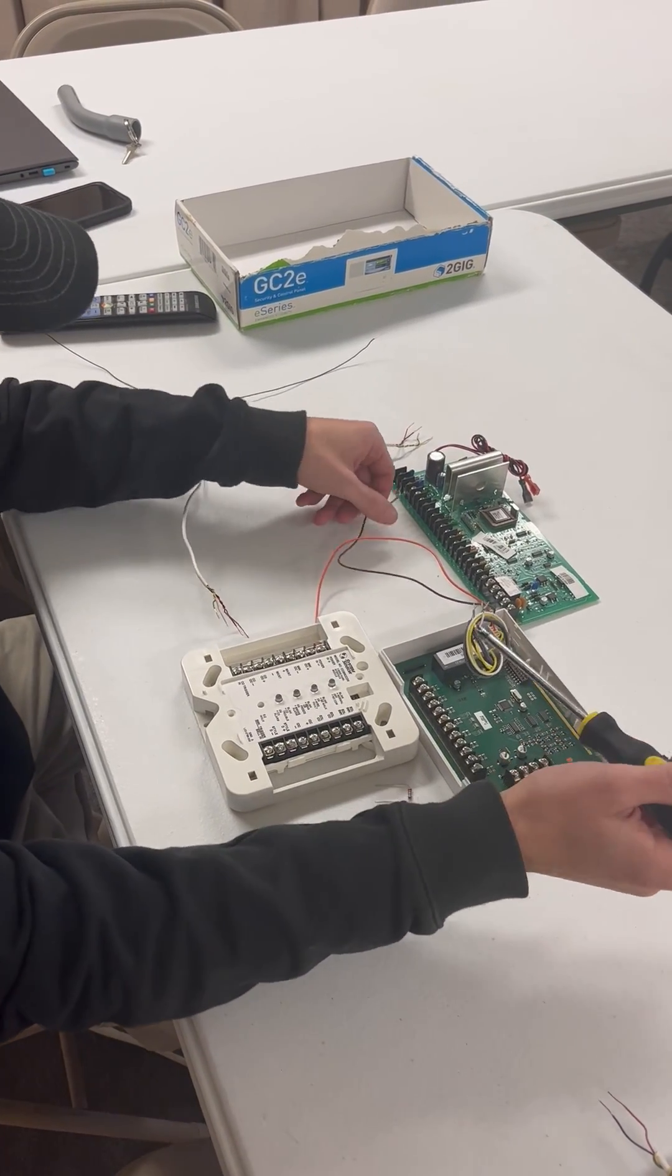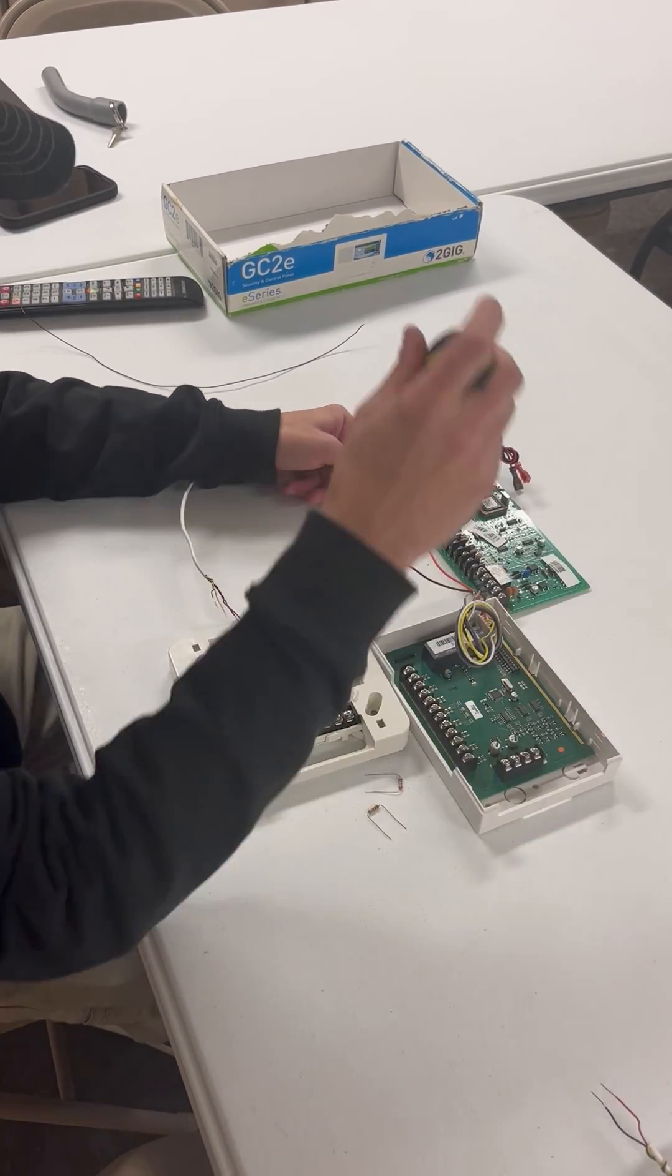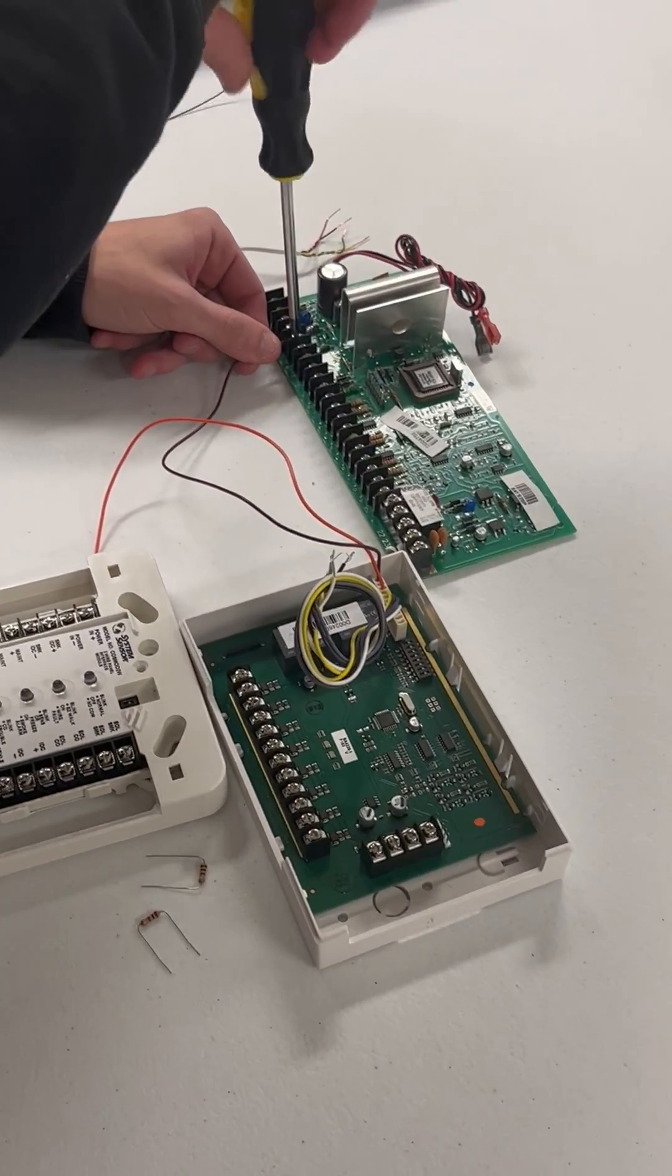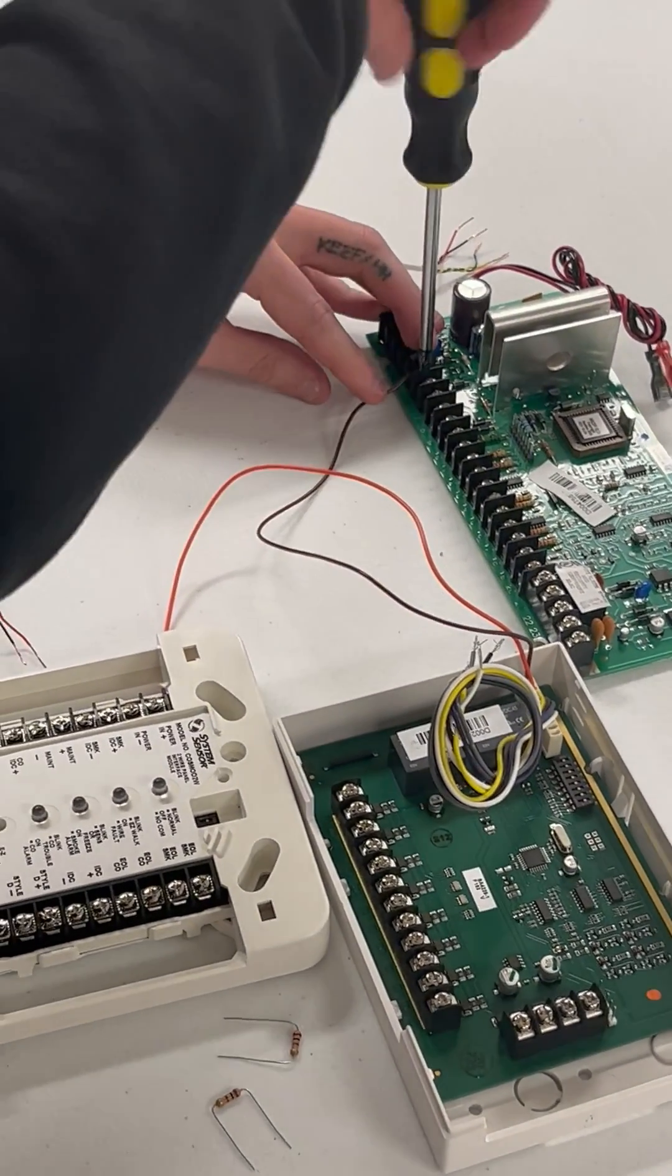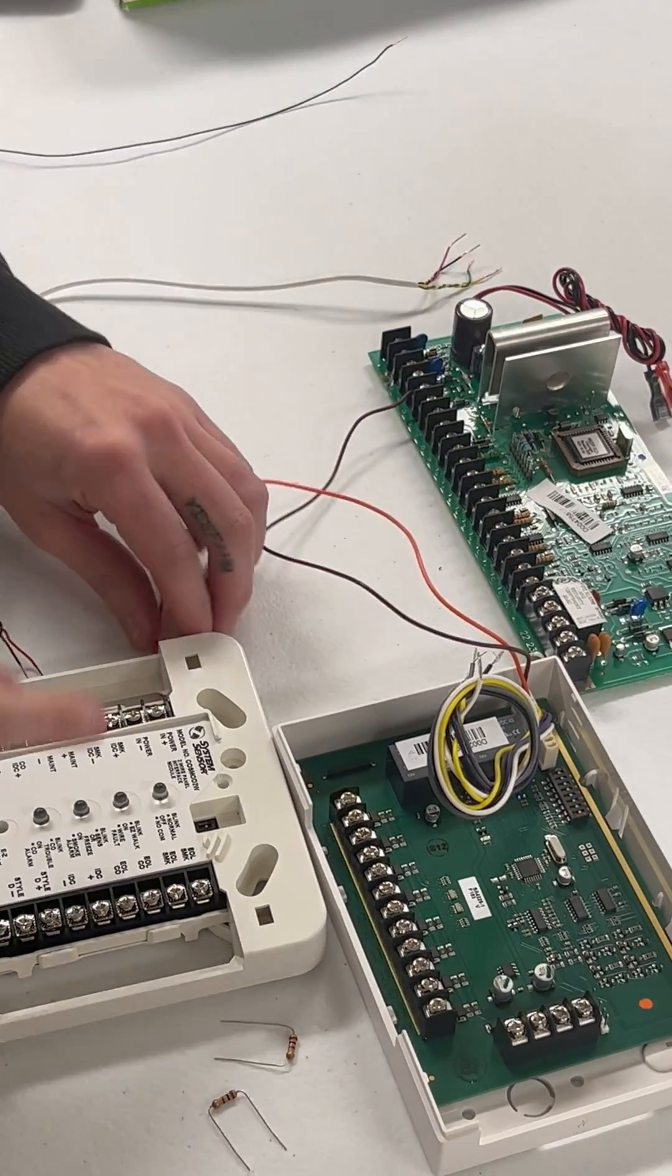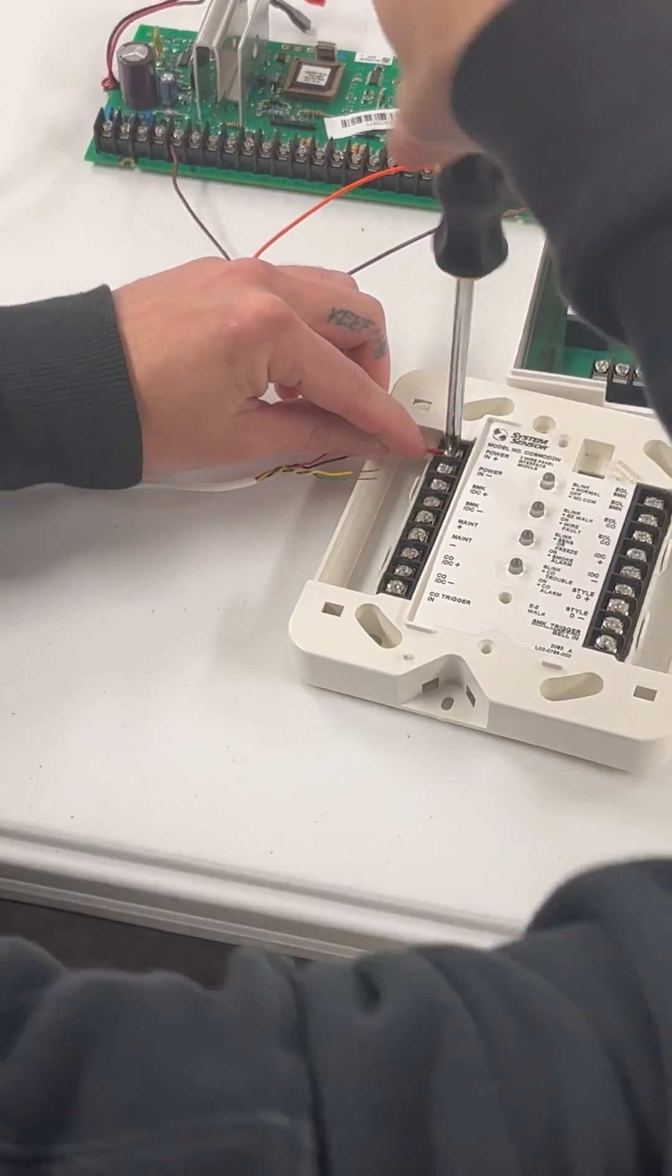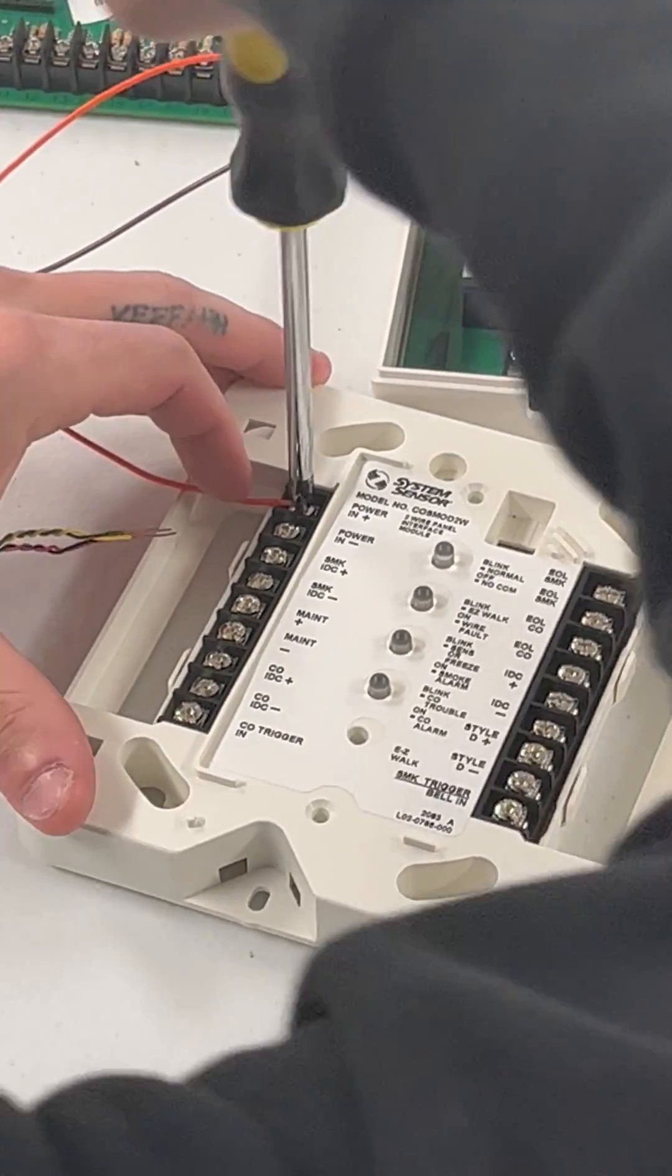We're going to start with our relay. We're going to wire the relay into our positive power coming out from the panel which is terminal five and we're going to go into the power in positive on the cosmod. The relay is what drops the power to the smoke detectors causing them to reset.